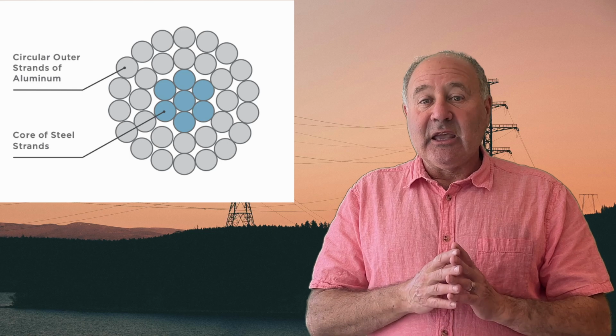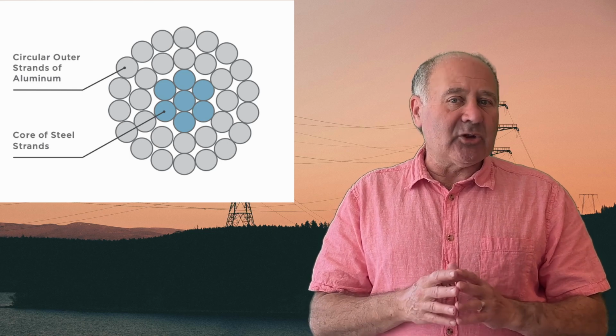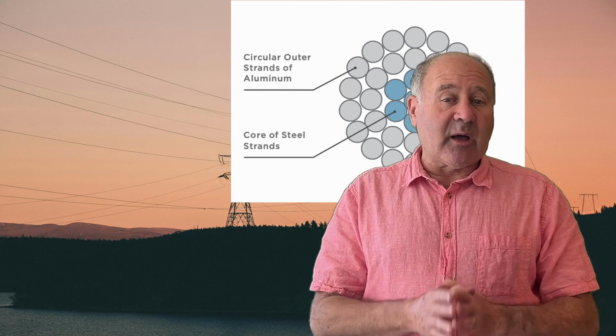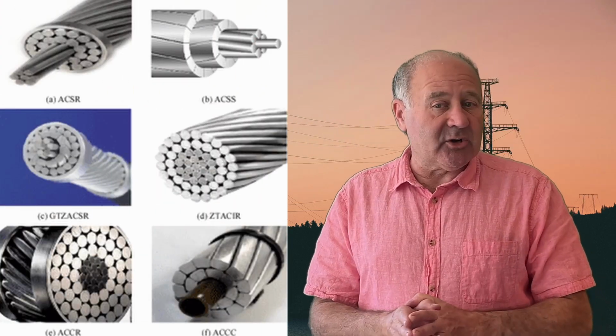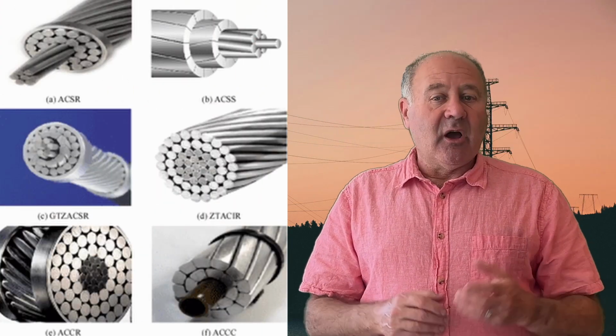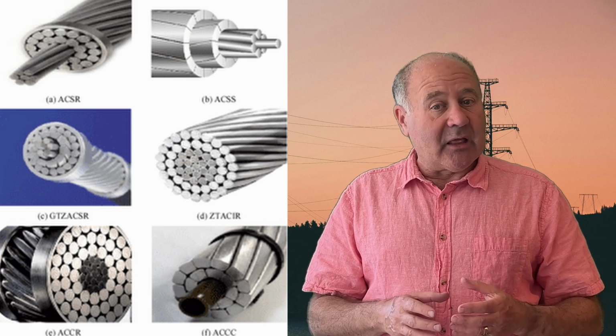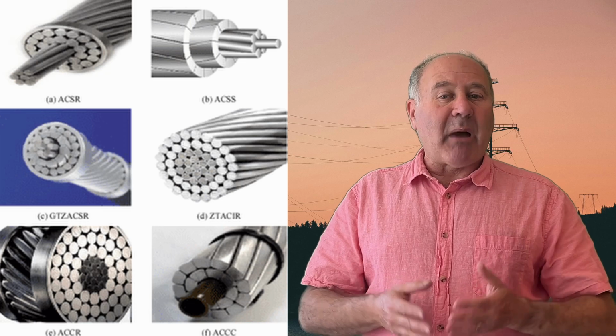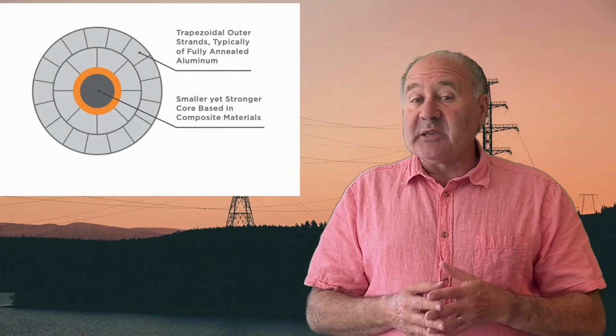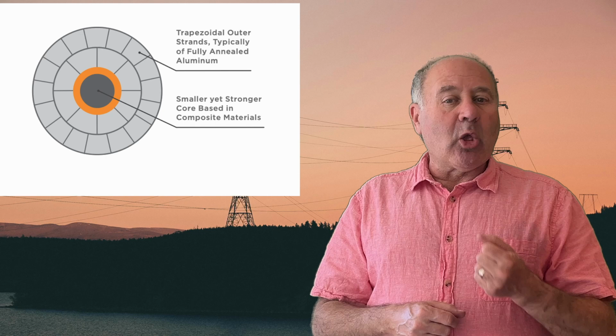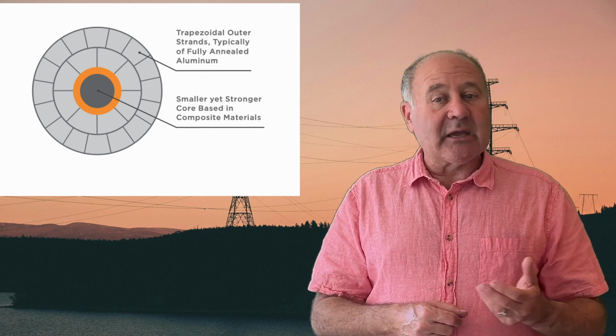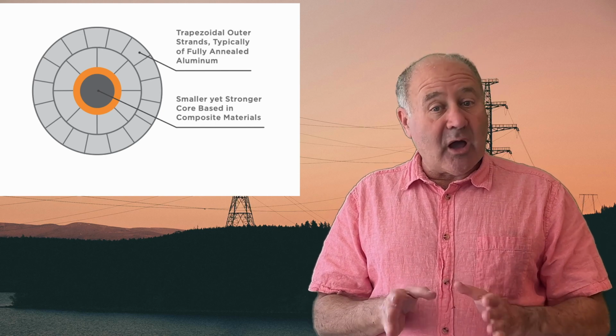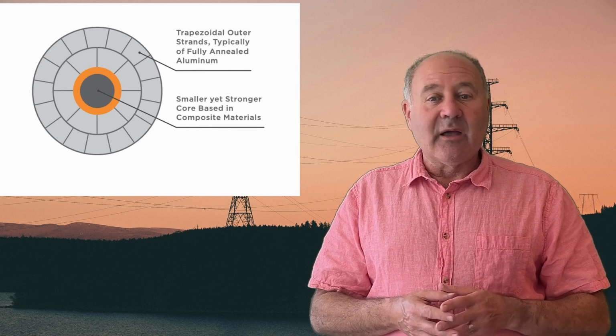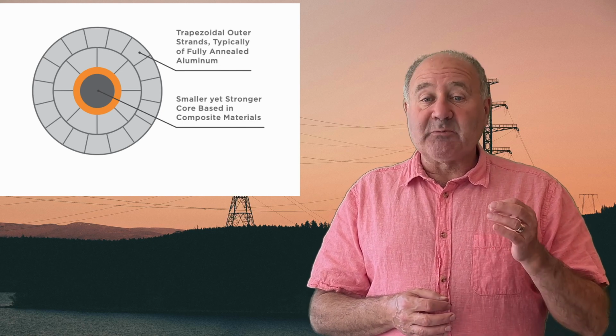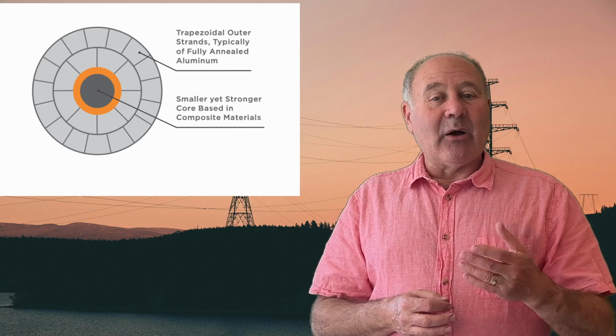Dynamic line ratings can increase the amount of power these cables carry, but not dramatically. In the last 20 years, several companies have introduced composite core conductors, which can carry up to double the current of conventional conductors on the same pylons, inside the same right-of-way, with only minor changes at the substations. These cables swap the steel core for a smaller, lighter composite core, typically ceramic, glass, or carbon fibers, without compromising structural strength. This means more conductive aluminum, which has been treated to allow it to get hotter, allowing for up to twice the current at the same voltage.